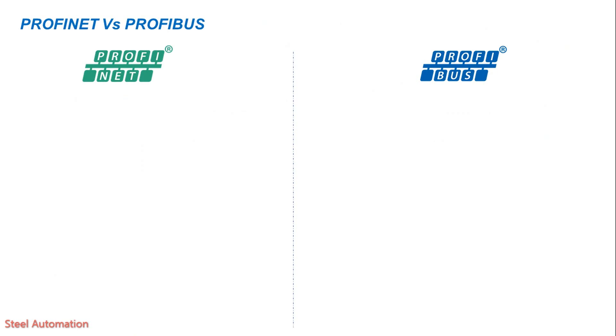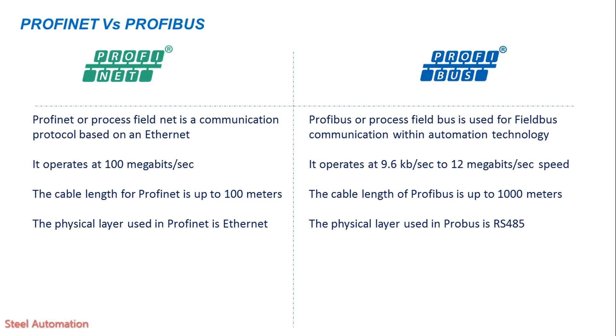What is the difference between Profinet and Profibus? Profinet is a communication protocol based on Ethernet, whereas Profibus is used for fieldbus communication within automation technology. Profinet operates at 100 Mbps, whereas Profibus operates at 9.6 kbps to 12 Mbps. The cable length for Profinet is up to 100 meters, whereas the cable length for Profibus is up to 1000 meters. The physical layer used in Profinet is Ethernet, whereas the physical layer used in Profibus is RS-485.